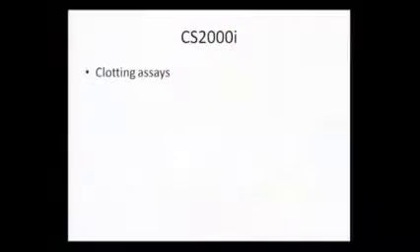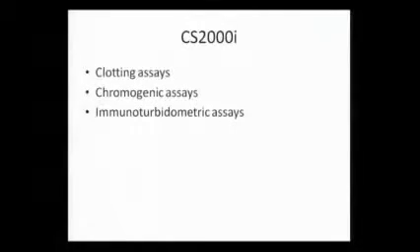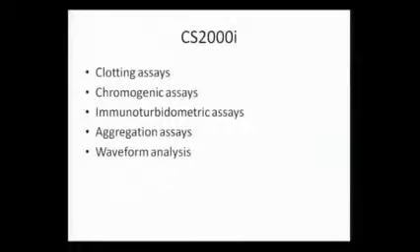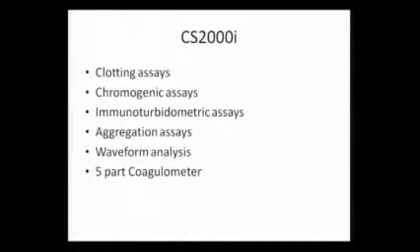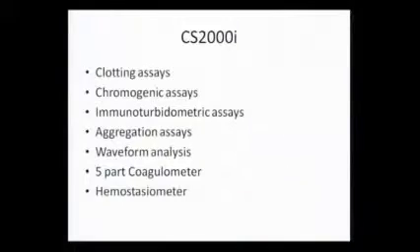The CS2000i for me does clotting assays, chromogenic assays, immunoturbidimetric assays, aggregation assays, and waveform analysis — meaning it also does global hemostatic testing. So for me this machine is what I call a five-part coagulometer. In the world of coagulation we have three-part and five-part analyzers, and I would take it further and call the CS2000 a full hemostatiometer — meaning any part of hemostasis that needs to be tested can be done on this single platform without needing another proprietary instrument.